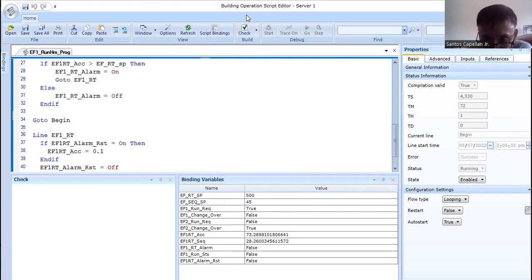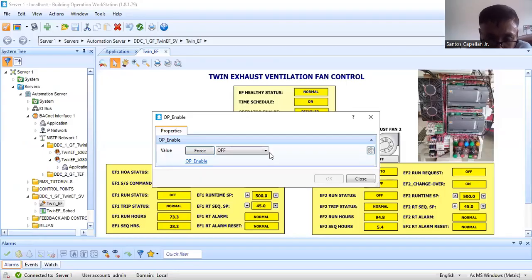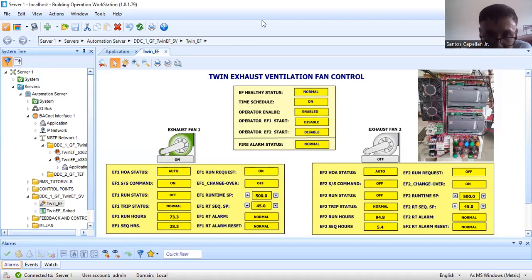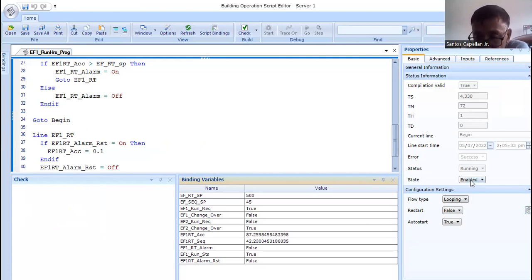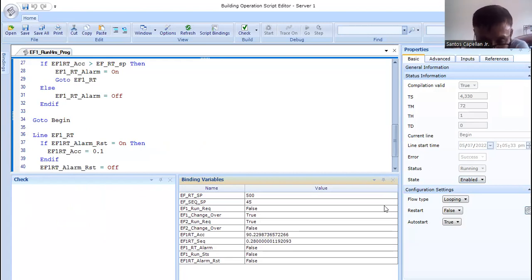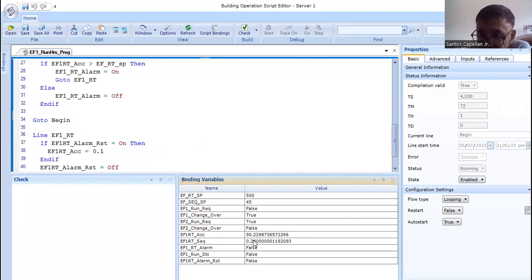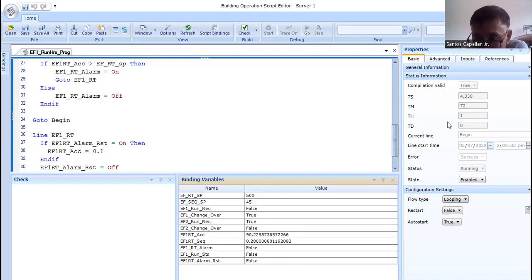In the program you can monitor and check the performance of the script. Right now it is disabled. Let me go back to my system to enable it. The operator enable was disabled — I will enable it so the system will work. Going back to the script program, you can see the variables are changing because all these script programs, when enabled, are uploaded to the controller and working in the background. EF2 is running now, as you can check in the graphics — the sequence has already reset.